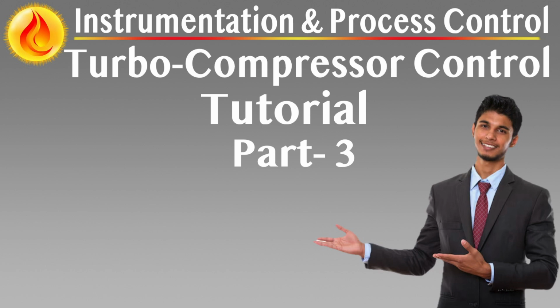Local and remote visibility. Operators can view the live status of auxiliaries, valve positions, flow indicators, and fault states from the UCP touchscreen interface, external DCS displays via OPC or Modbus links, maintenance terminals or engineering stations. Trend and diagnostic support: auxiliary system data is logged and trended continuously, enabling proactive detection of deteriorating pump performance, filter clogging trends, oscillations in supply pressure, and anomalies in backup activation frequency.